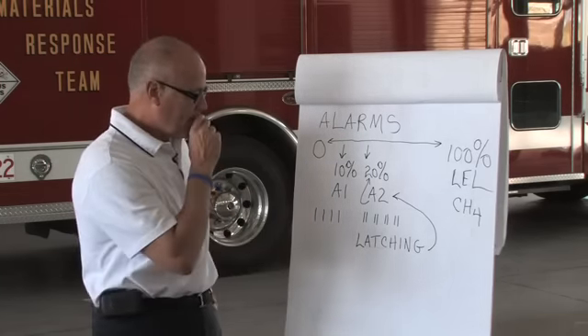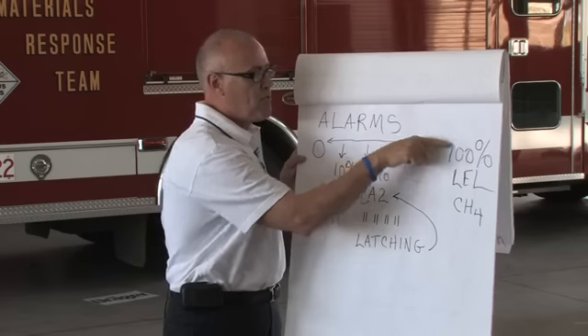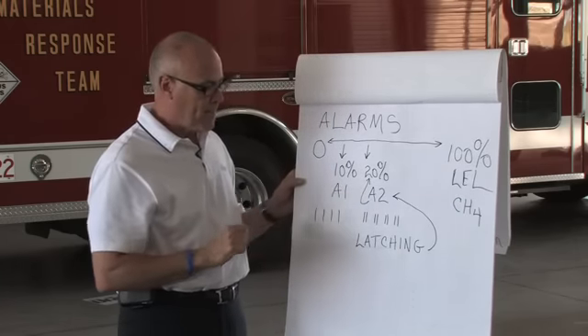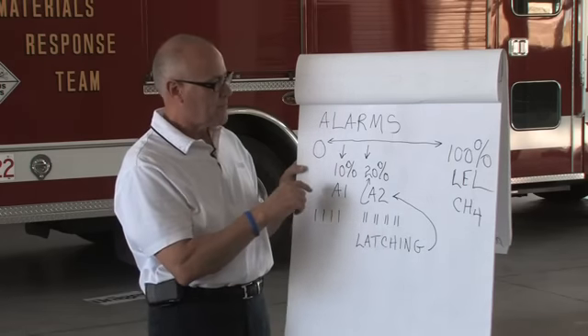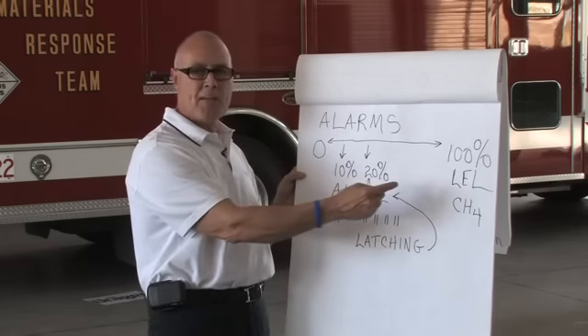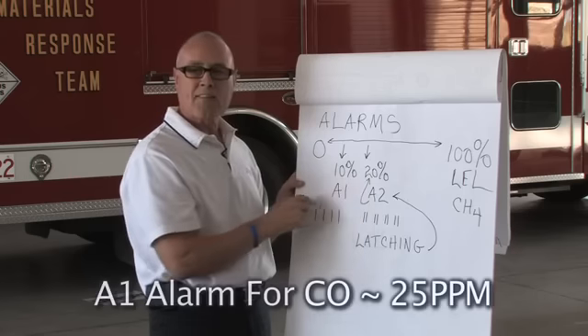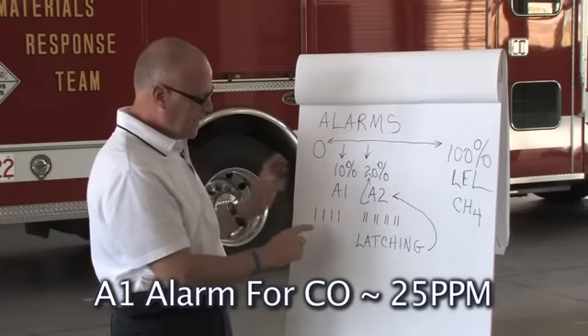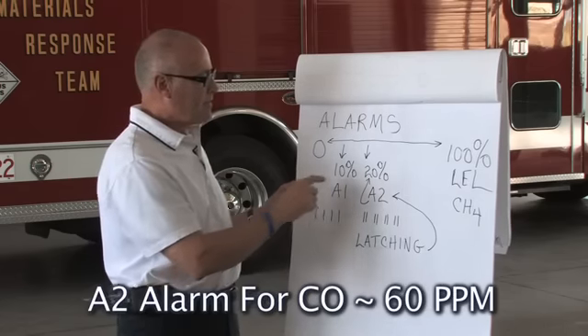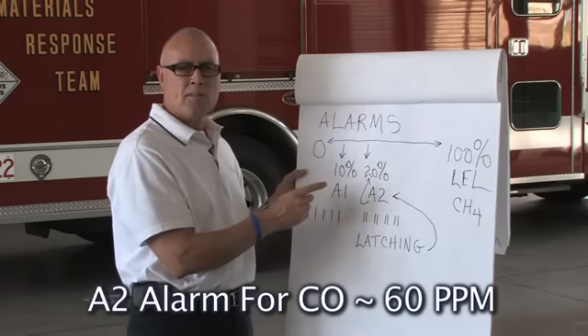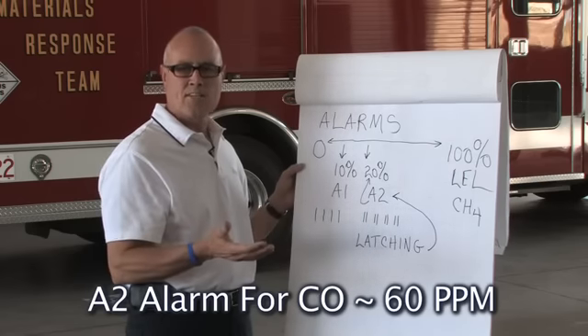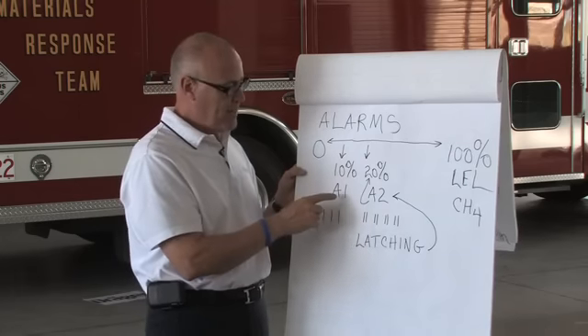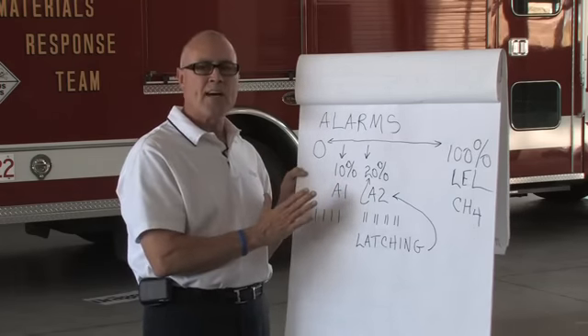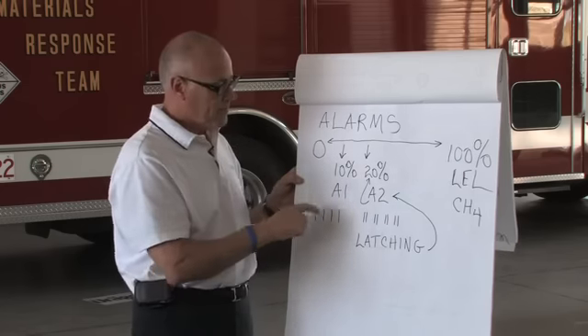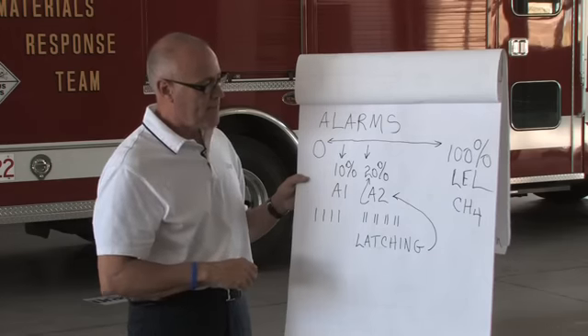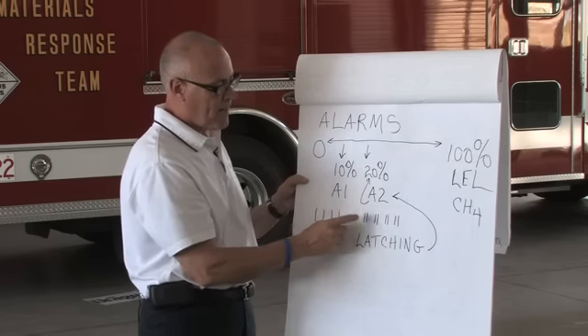Now, one thing I need to make a note of, we're starting from a 0 gas up to full scale. So I didn't write carbon monoxide in here and hydrogen sulfide, but I want to talk about them a little bit. Carbon monoxide is a 0 to 500 ppm scale for CO. So your A1 alarm for carbon monoxide will be 25 parts per million. You will get your single pulse alarm, and 60 ppm is the A2 alarm for carbon monoxide on most Draeger meters, unless the user goes in and changes it. You can go in and change it, but 25 ppm on the A1 is pretty much a state law in California not to exceed. So that's your A1 alarm. A2, 60 ppm on carbon monoxide. That will be the latching alarm, and you'll also get your double tone pulsations.